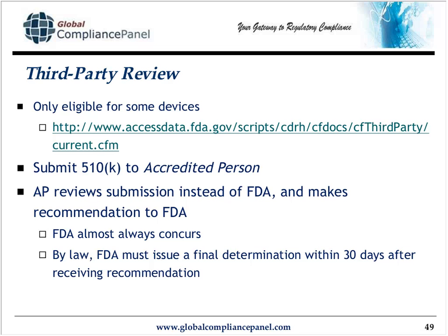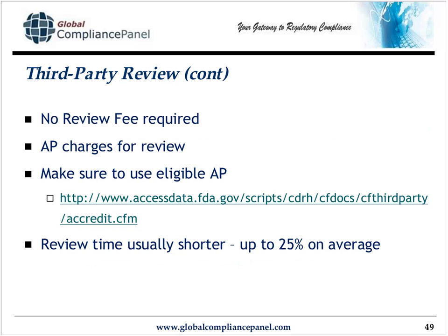By law, the agency has 30 days after receiving the recommendation. I don't know what you would do to them, but by law, they have 30 days. Like I said earlier, you don't have to pay for the 510K review, but you do have to pay the accredited person or company for their review.